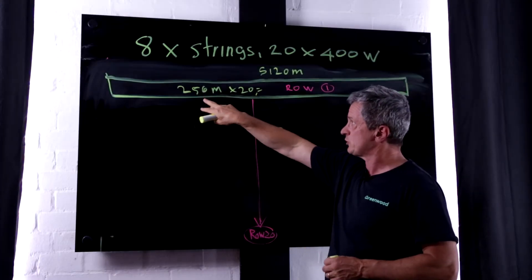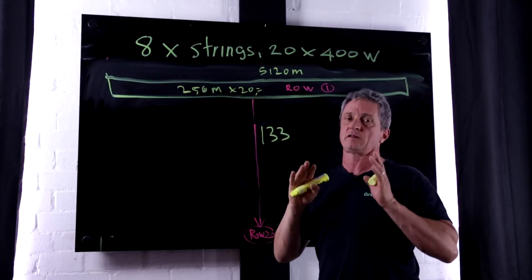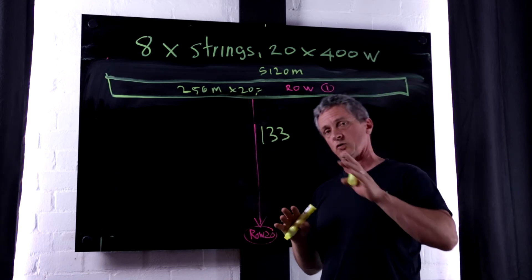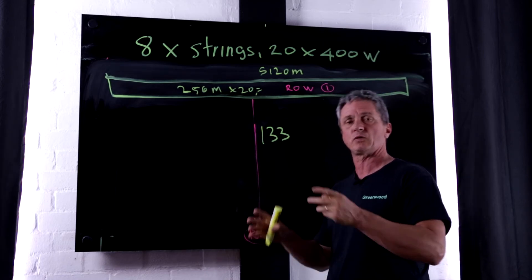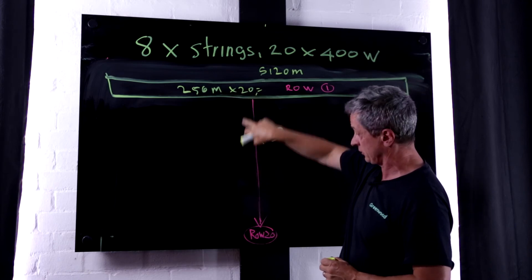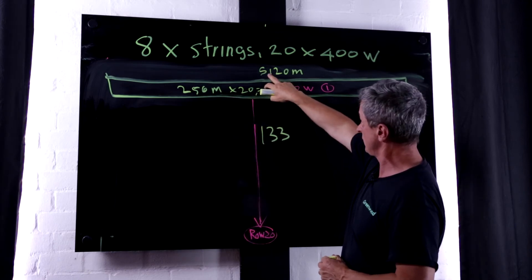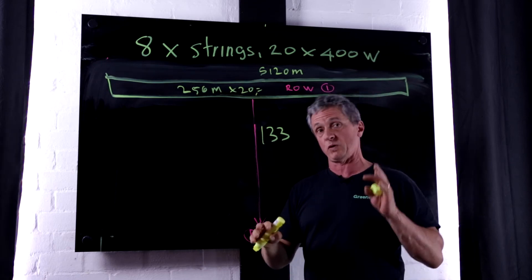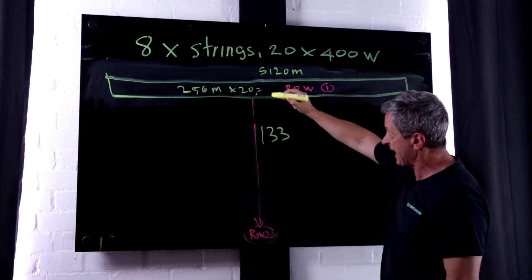So we've established that each row is using 256 metres of cable, and I'm not talking about the earth here, that's additional, we're talking about the positive and the negative. And obviously, we multiply that by the 20 rows, and we're using all up 5,120 metres of cable just within the rows.